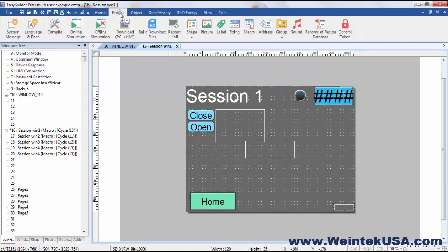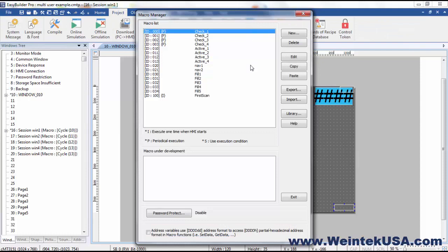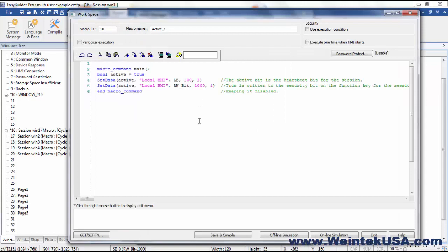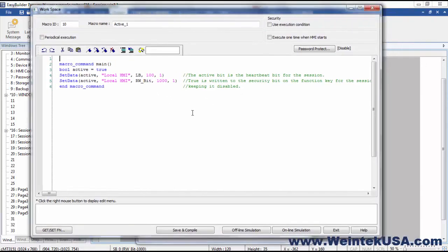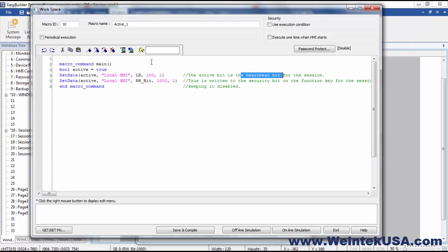So what I've done is I've created some macros, and when this session window cycles, macro 10 is active, is cycling. And all it is doing is turning on a bit that we're going to use in another macro, LB100. This is the heartbeat bit for the session. As long as this bit is active, our other macro will know that this window is open. So every scan of the processor, when this window is open, it's going to write a value of one to each one of these registers.